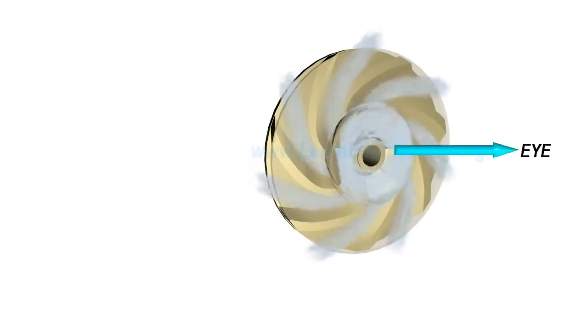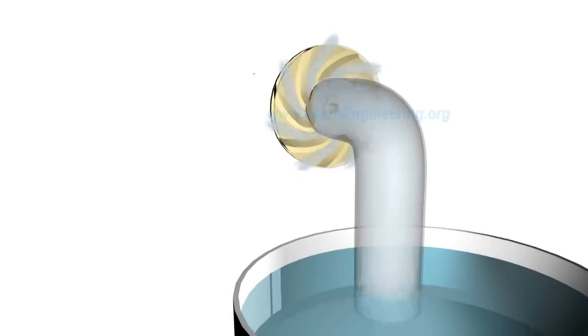At suction side, water is getting displaced so a negative pressure will be induced at eye. Such low pressure helps in sucking fresh water stream into the system again and this process continues. This is the reason why priming is important for centrifugal pumps. If no water is present initially, the negative pressure developed by rotating air at eye of impeller will be negligibly small to suck fresh stream of water.